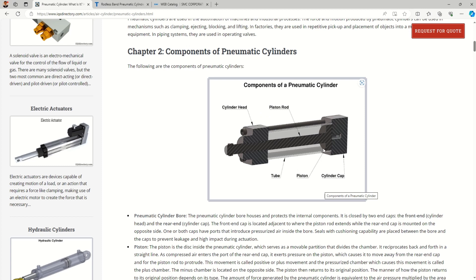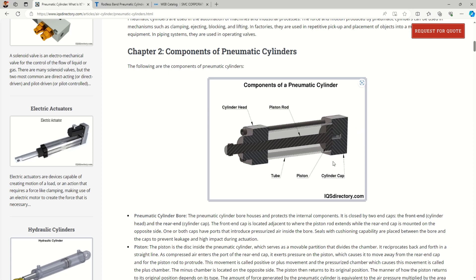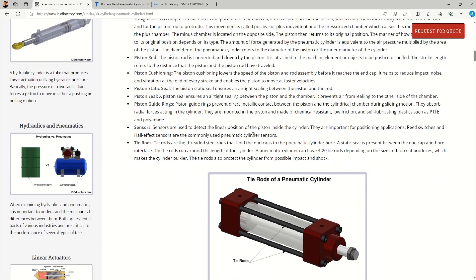Many people get confused between the piston and the piston rod — the piston is the disc inside the tube and the piston rod extends out from it. Whenever you select a pneumatic cylinder, it is specified by its bore and stroke. The bore is the inner diameter of the tube — for example, a bore of 50 means the ID of the cylinder is 50 mm — and then we have the stroke according to our requirement.